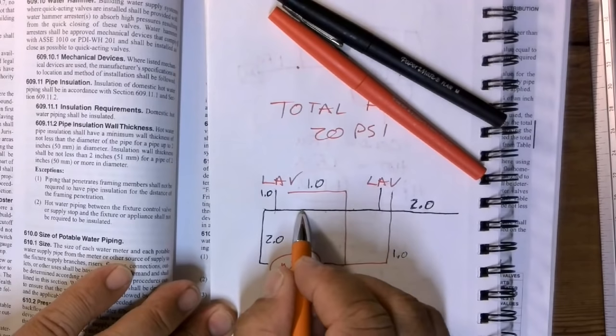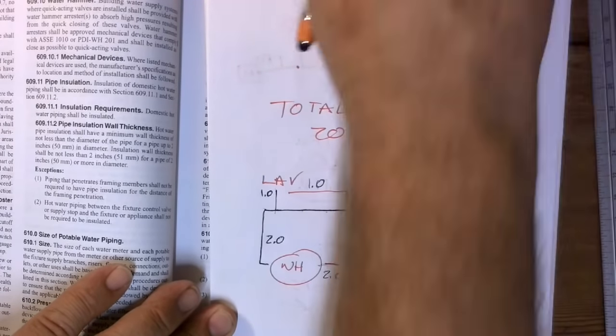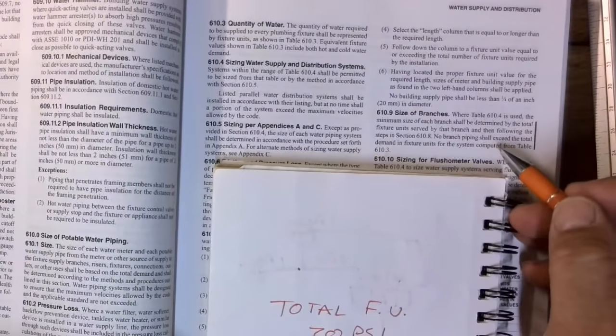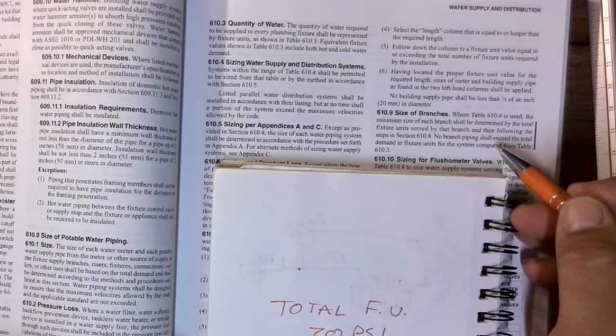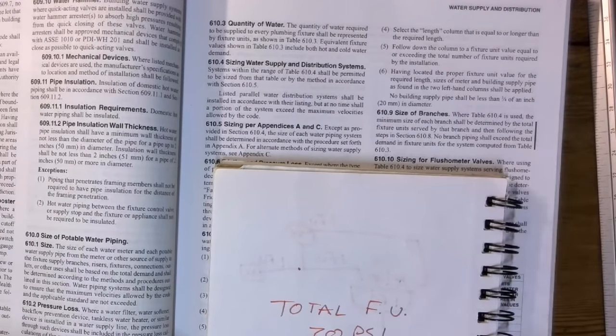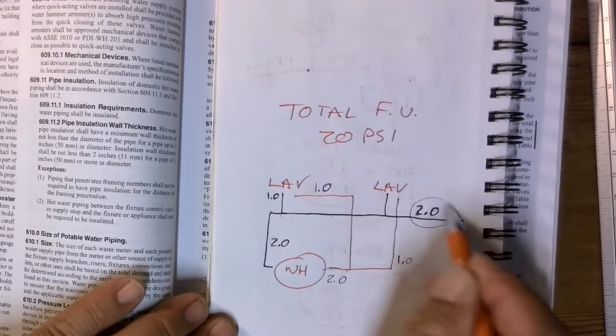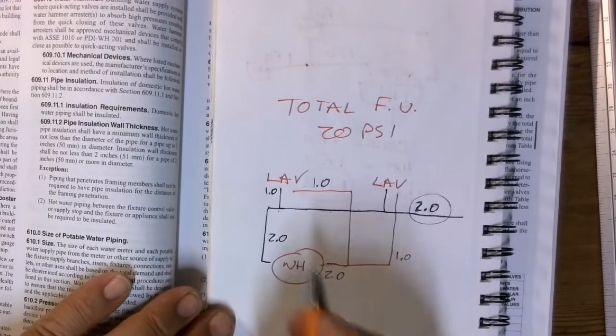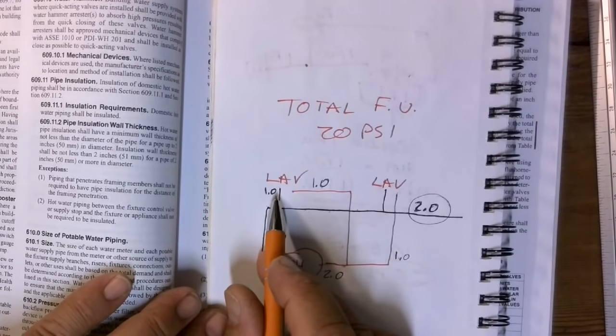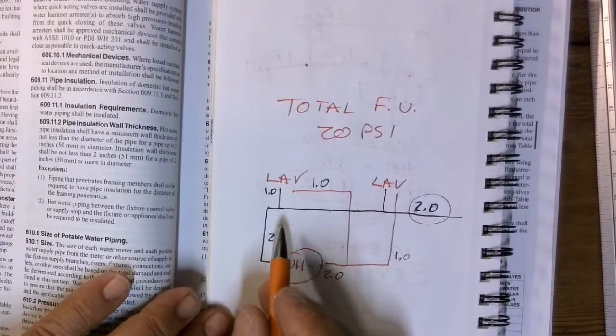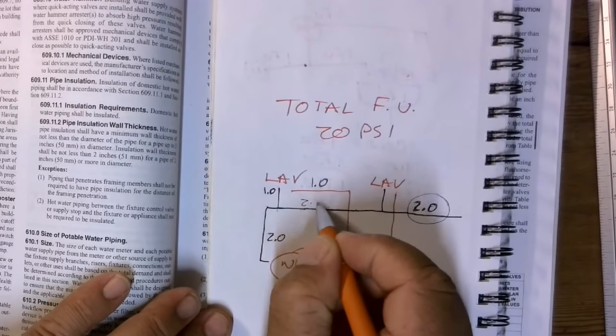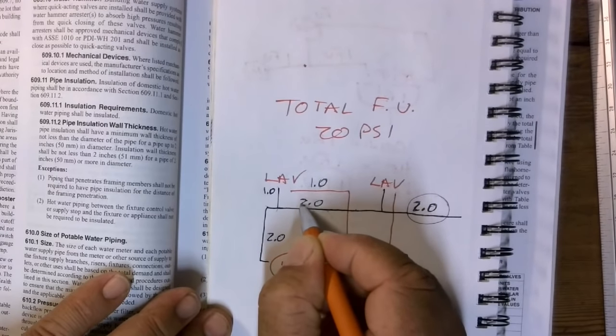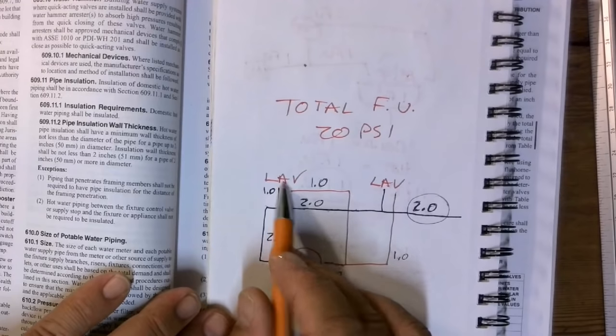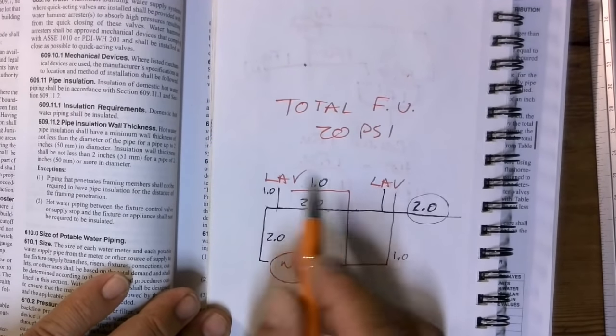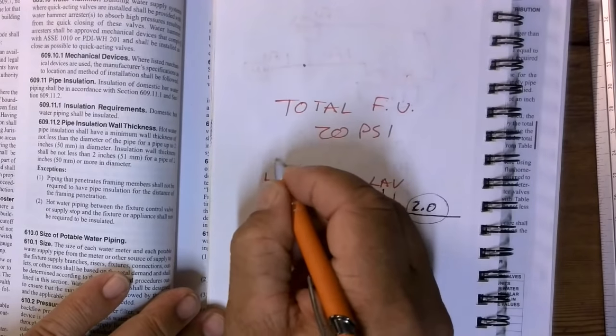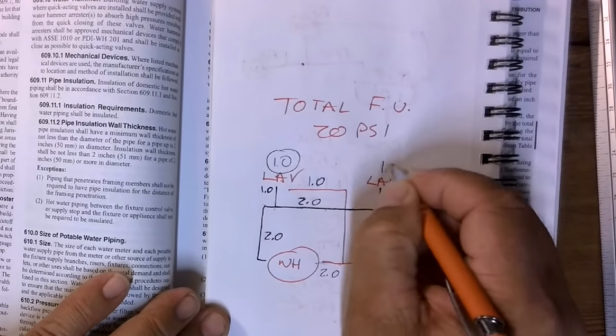How many fixture units are on this one? This code section that we just read says no branch piping shall exceed the total demand in fixture units, right? I told you my total demand was two. So even though I have one here and two here, it's going to be two, because the value of this lav, no matter if it's coming this way or this way, is still one.